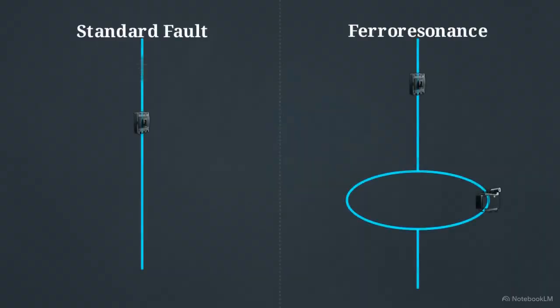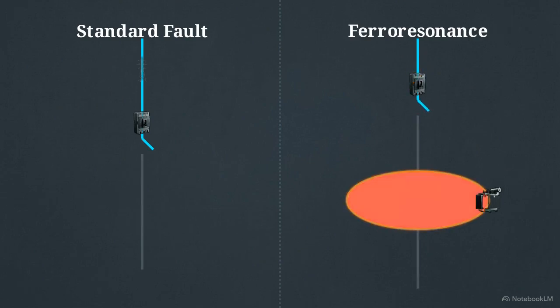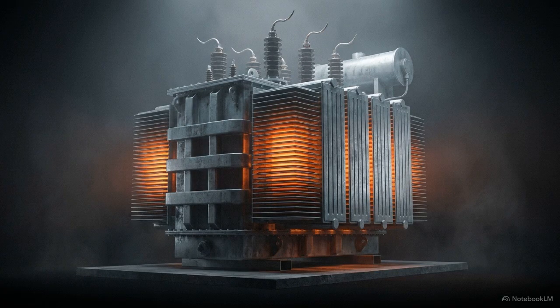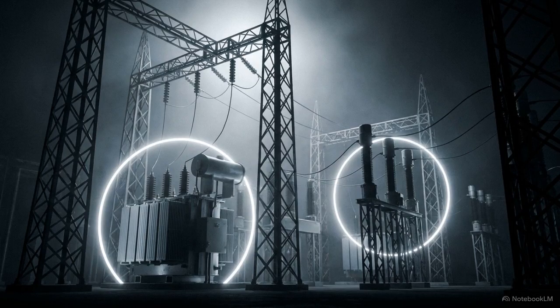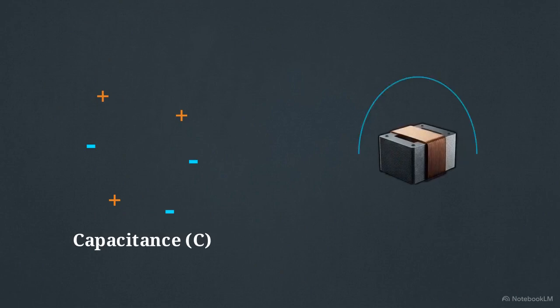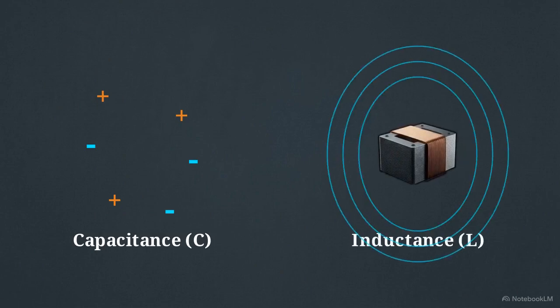When a standard electrical fault occurs, the system is designed to trip and clear the issue in a fraction of a second. Ferroresonance behaves differently. It is an undamped transient that actively feeds on its own energy, locking the grid into a cycle that refuses to die out naturally. To trigger this event, two specific components of the grid have to interact. First, you have the capacitance of the transmission cables, which naturally store electrical charge. Second, you have the inductance of the transformer's magnetic iron core.